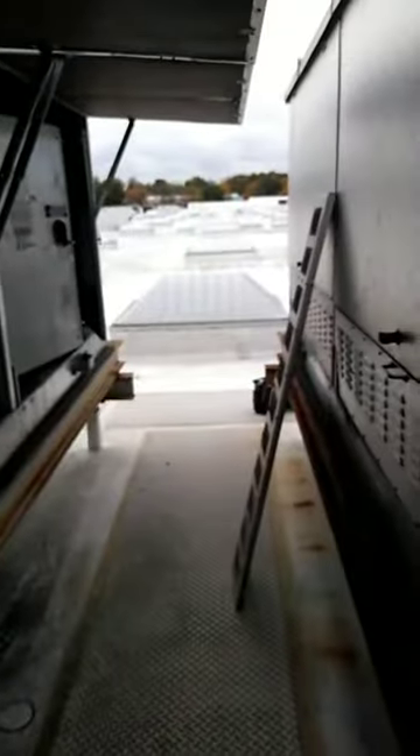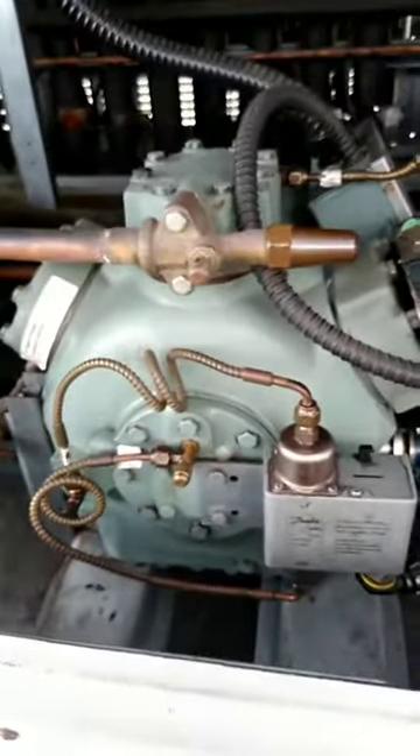I'm going to order that compressor. It's a 06DR. It's going to be a pain in the ass — it's so tight in there. But I looked in the Carlyle service manual and it's 190 pounds, which I thought would be a little more than that. So I'm going to have to get a compressor for this.